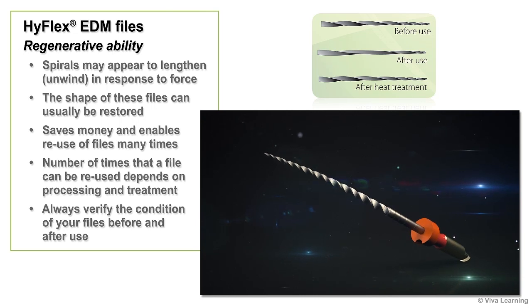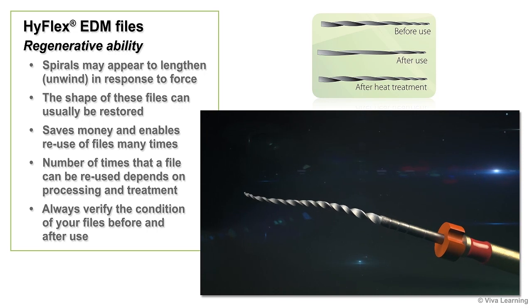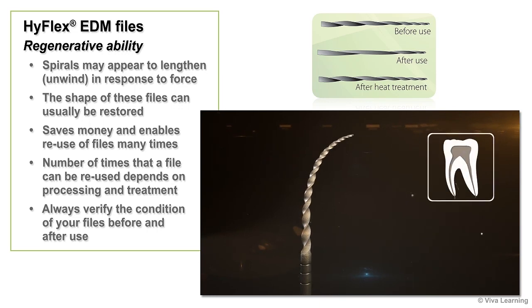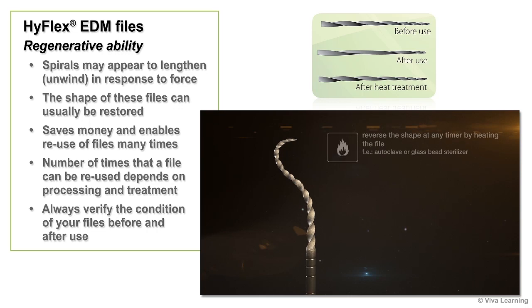As you use the HyFlex EDM files, you'll see that their spirals may appear to lengthen or unwind in response to force. But unlike other commonly available NiTi instruments, the shape of these files can usually be restored. Provided the spirals do not wind in the opposite direction during use, they will regain their original shape during normal autoclaving or when a glass bead sterilizer is used for 10 seconds. This regenerative ability saves you money, enabling you to reuse files many times.